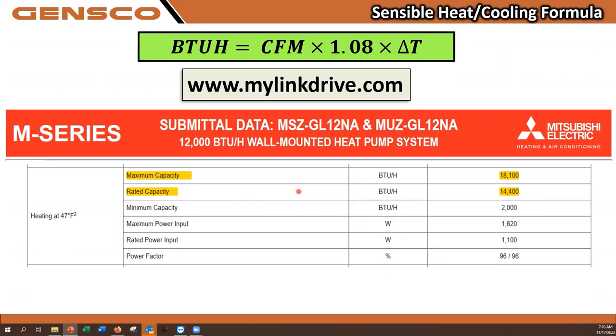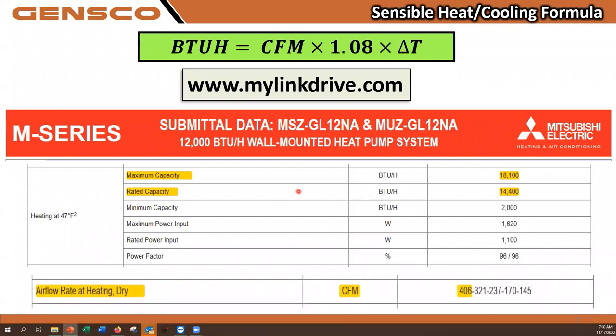14,400 BTUs. If I go to the airflow section, I want to look at the high-speed fan. Since our first example is going to be a heating output check, it's going to be a dry coil. There will be a different CFM number for a wet coil when you're running it in cool mode, and you'll see that in a little bit. So we find out what the actual unit's rated for, what the high-speed fan is rated for, and verify the unit is clean. The 406 number is the number we're going to be sticking in this formula when we do another step.